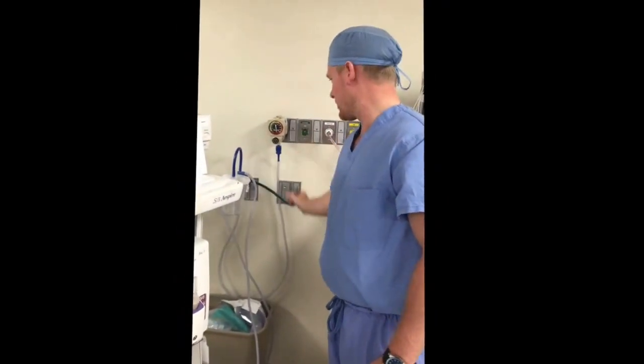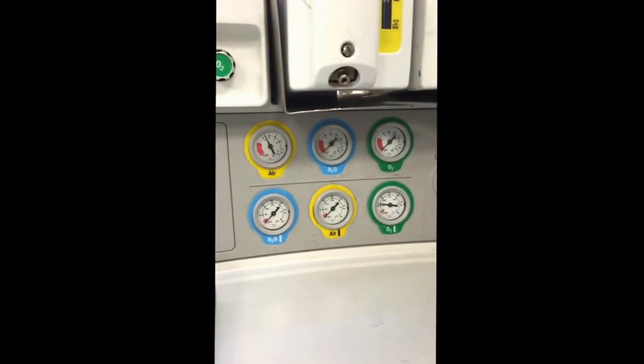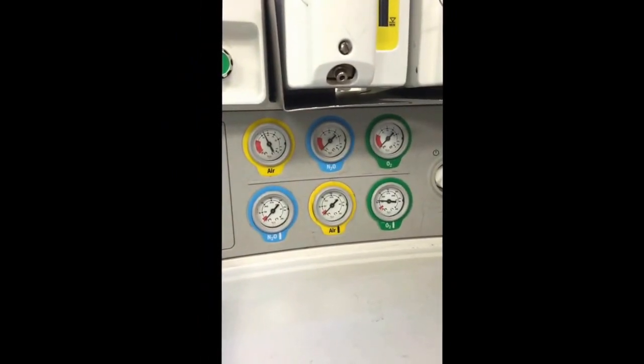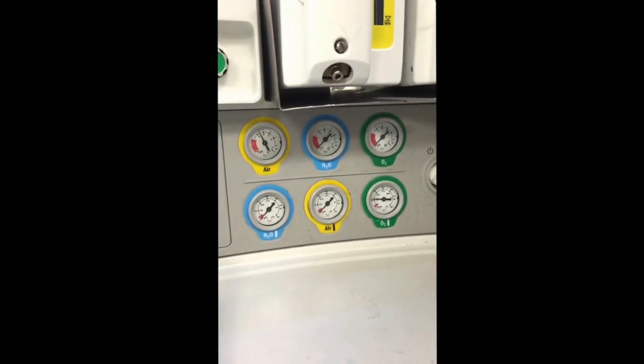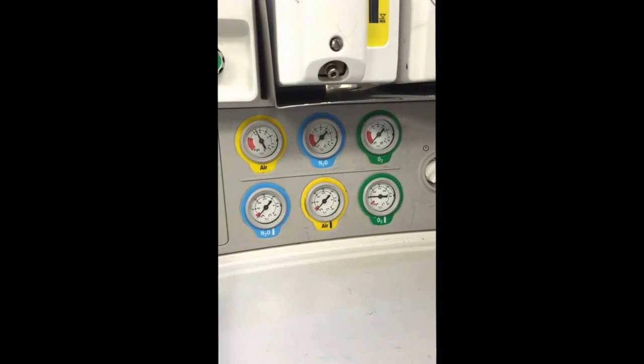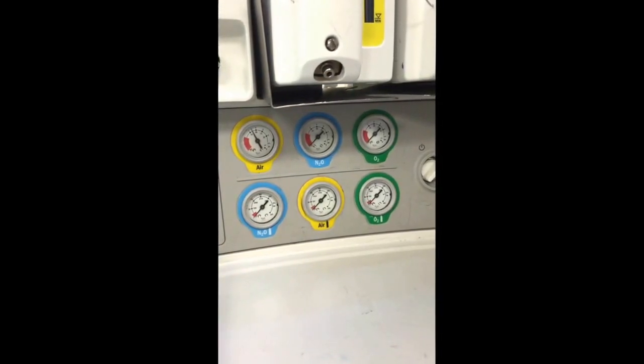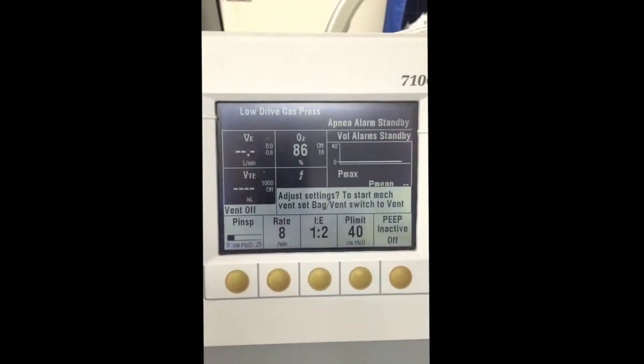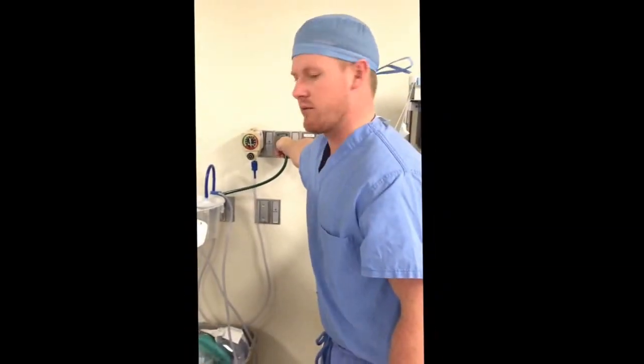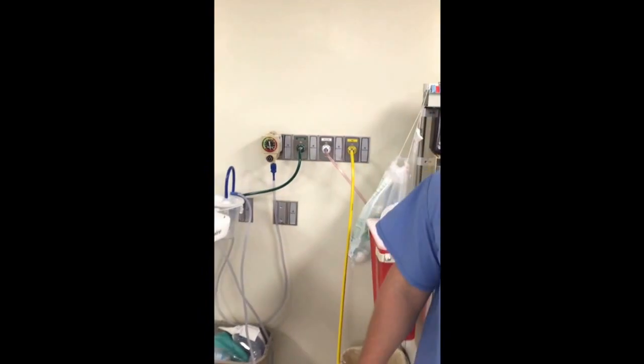So at this point, you can unplug your pipeline pressure, hit your O2 flush valve, and I'm waiting for the machine to turn on so we hear our low O2 pressure alarm. You'll see the pressure go down from the cylinder and you'll hear the machine alarm. And as you can see, low drive gas pressure. And then you can plug back in to the pipeline. So that's a safety feature in case you would lose driveline pressure. It would automatically alarm and you know you have a full cylinder to turn to.